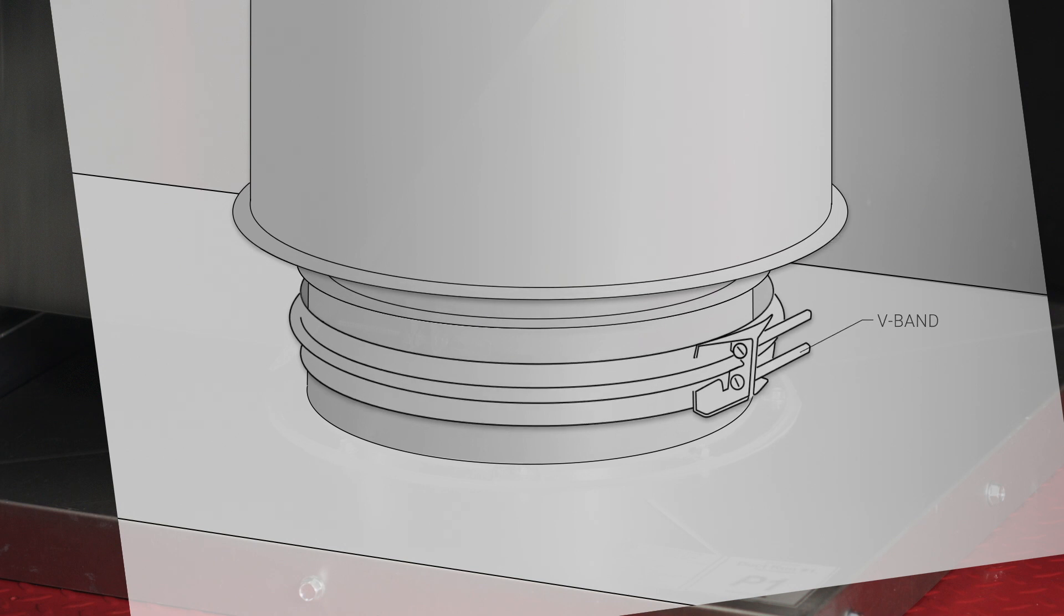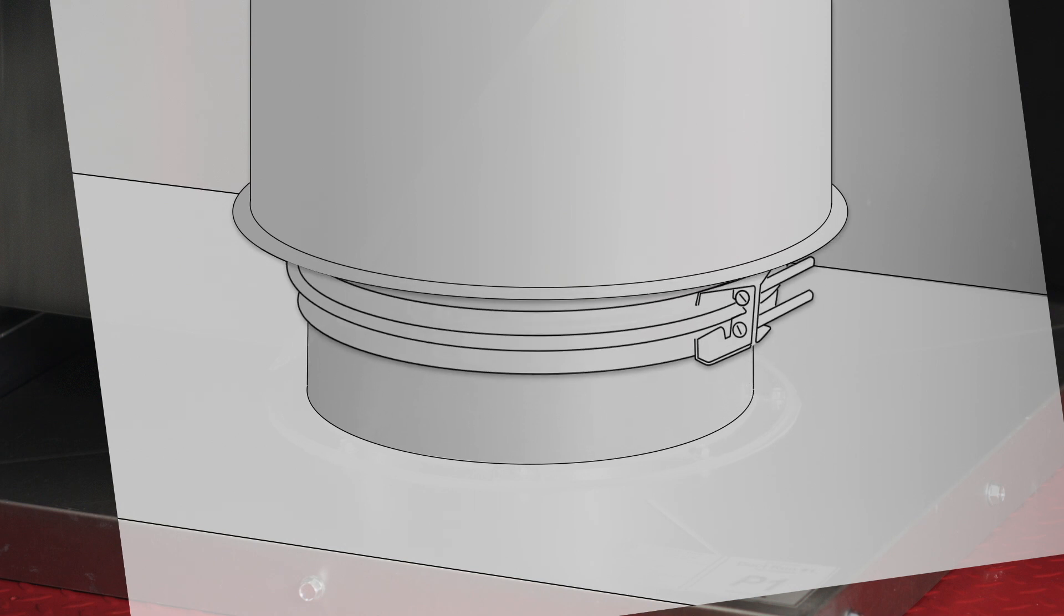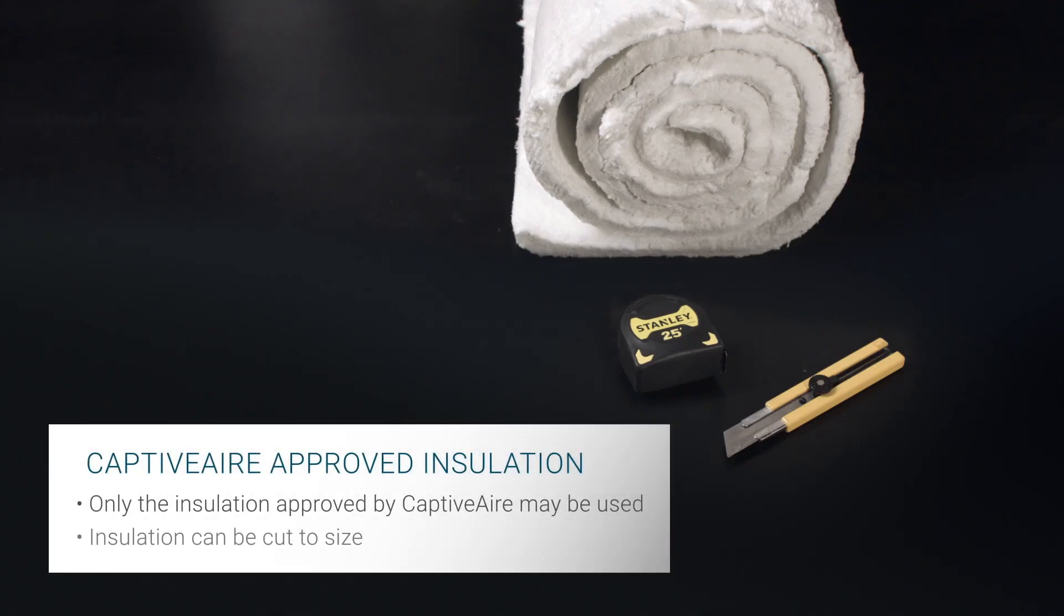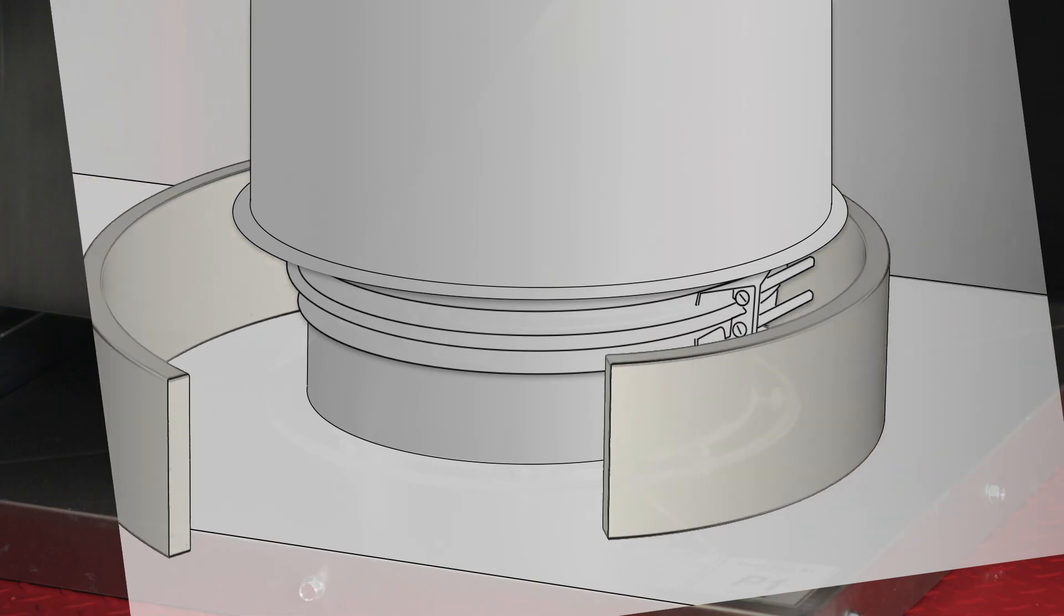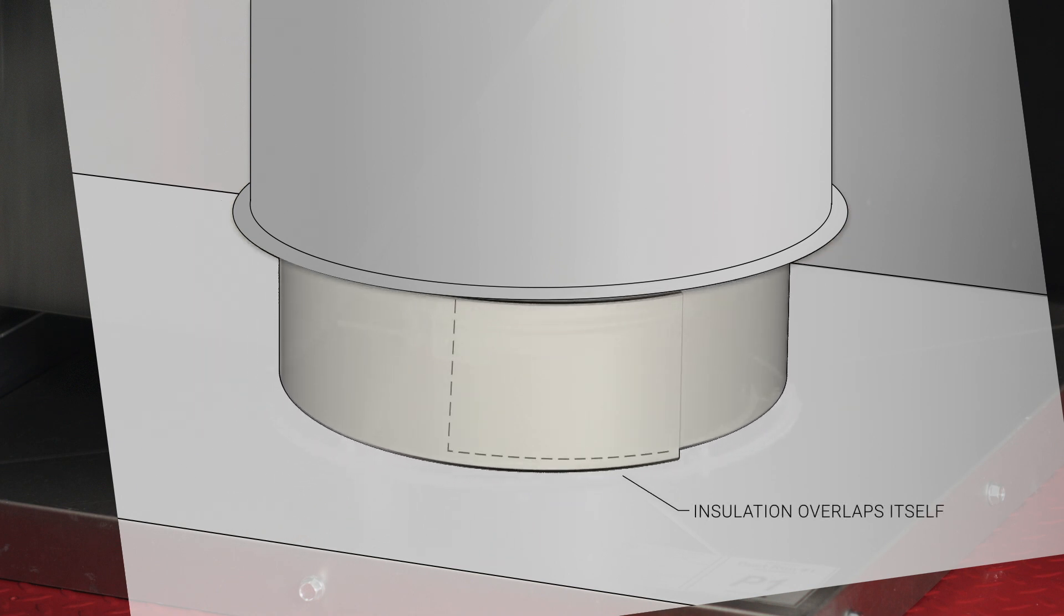Once the riser and connecting duct sections have been connected, cut the provided insulation to size. Tightly wrap the insulation to completely fill all voids. Be sure that the remaining ends overlap, and that the insulation is the same type and number of layers as the rest of the duct.